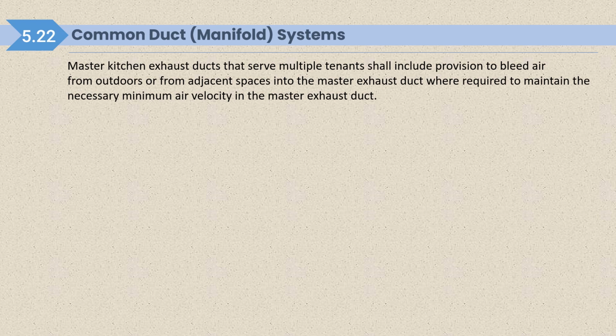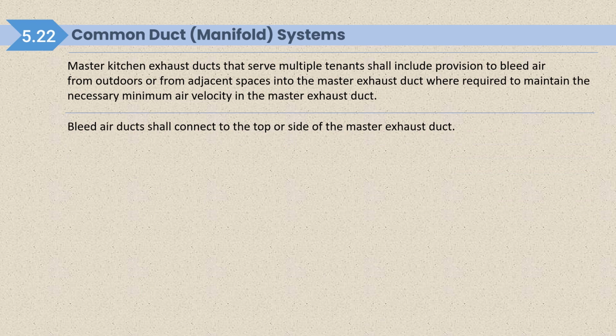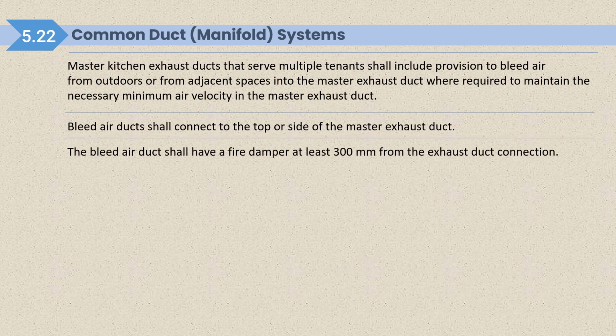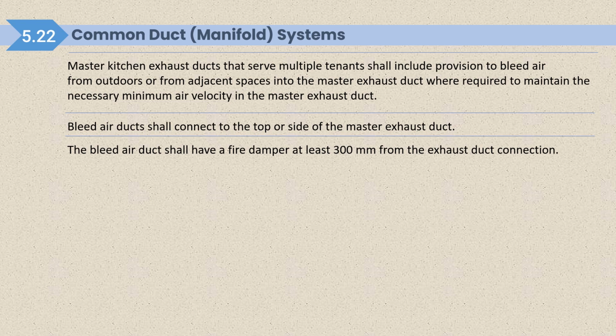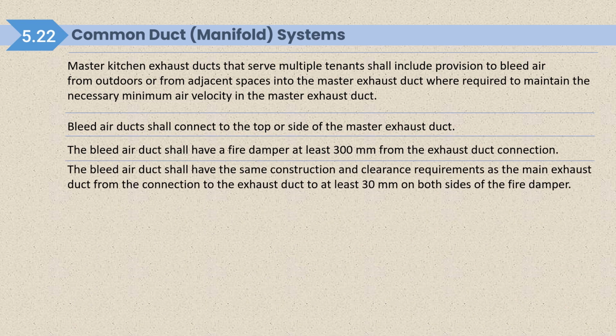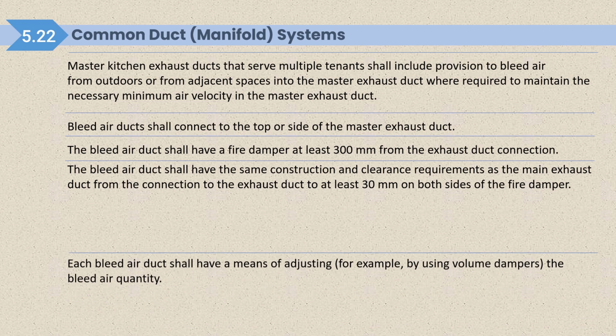Bleed air duct shall connect, sorry, bleed air duct shall connect to the top or side of the master exhaust duct. It cannot be connected through the bottom. The bleed air duct shall have a fire damper at least 300 mm from the exhaust duct connection. The bleed air duct shall have the same construction and clearance requirement as the main exhaust duct from the connection to the exhaust duct to at least 30 mm on both sides of the fire damper.